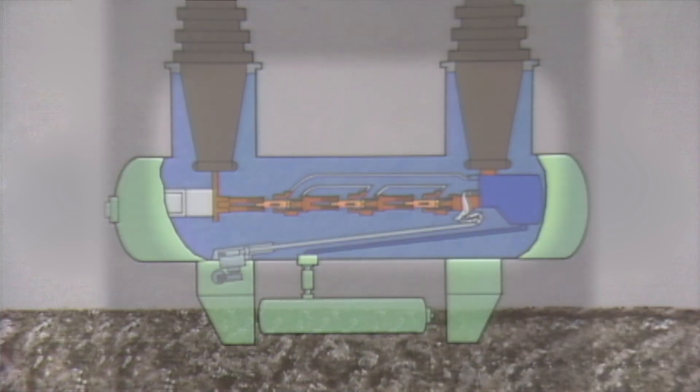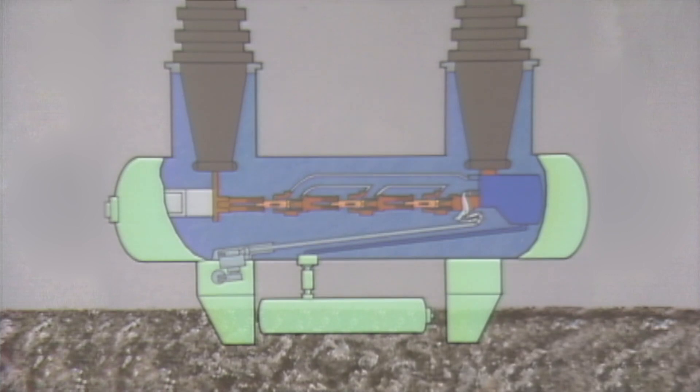The interrupting mechanisms are enclosed in a tank that is filled with SF6 gas at a low pressure. The main arc extinguishing features include several sets of contacts, a reservoir of high pressure SF6 gas, a blast valve, and blast tubes.